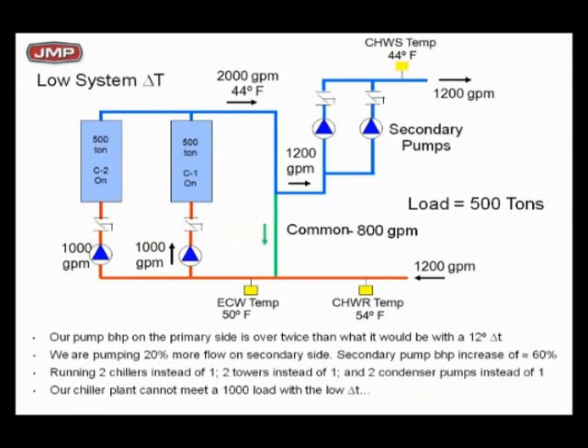So our chiller plant cannot give you 1,000 tons at low delta T. Remember that. If I only got 417 out of it, if I double that, I can only get about 835 out of it. In other words, I'll never get 1,000 tons out of this 1,000-ton chiller plant until you give me a hot return water, till you give me my 56. If you're going to insist on giving me 54, I cannot give you 1,000 tons. That's what you've got to kind of understand.